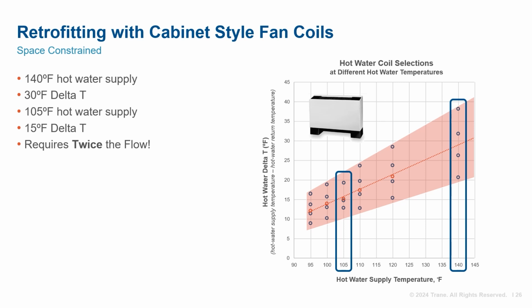At this temperature, the coil will require twice the hot water flow at design. It's important to note this is the worst case equipment, since it's typically the most space constrained. For example, coils in the central air handlers can be designed for 30-degree delta T with 105-degree hot water. For our fan coil example, one may be thinking with twice the flow, won't the pumping power double? Won't that wipe out energy savings of using the lower supply temperature? The answer is no, not even close. We will go over that in a minute.